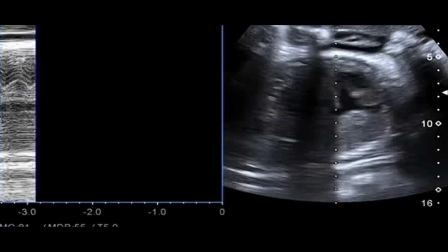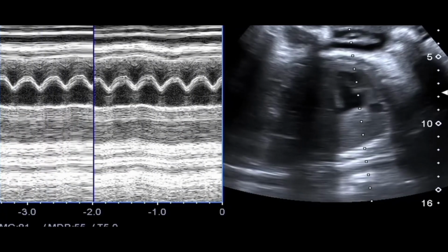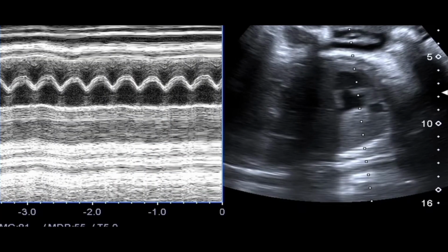First, focus on the fetal heart. Then, activate the M mode. The fetal heart should be positioned on the sonographic marker and the heartbeat waves are visualized on the screen. Freeze the image. The distance between the peaks can be marked, and the machine counts the heart rate, which is displayed directly on the screen.